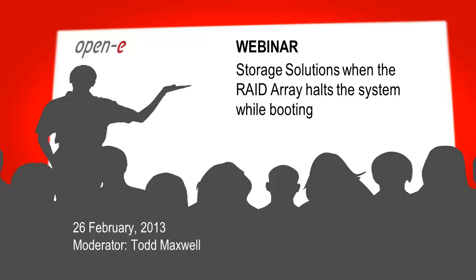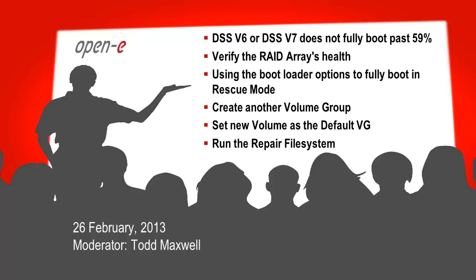One of the main causes of this — we had some cases about a month ago where two back-to-back customers, when they booted up the system, had issues with their RAID array and it did not fully boot past 59%. We're going to talk about how to get around that, what to do, and some resolutions so you can diagnose your RAID array and see if there are any drives that have failed or if the RAID itself has issues.